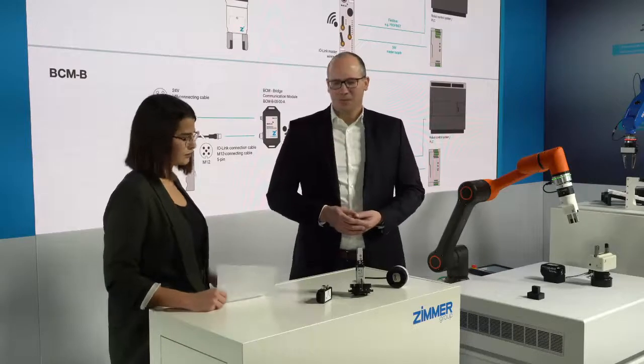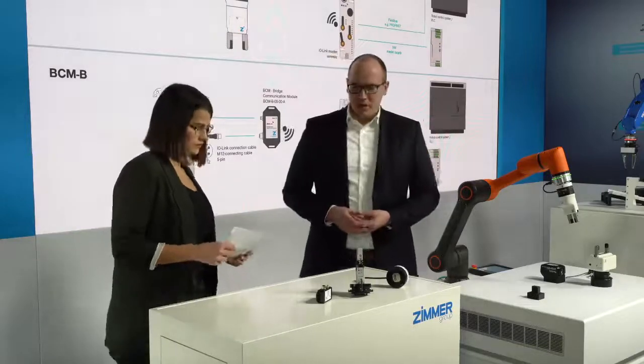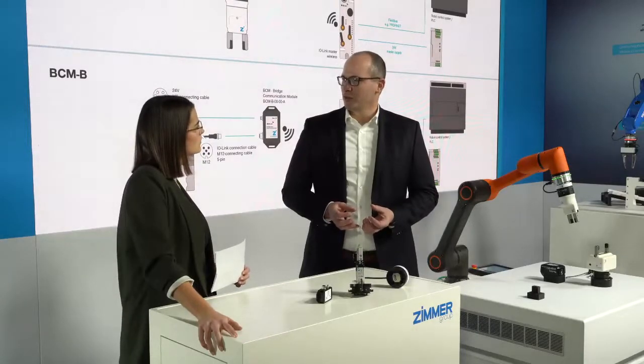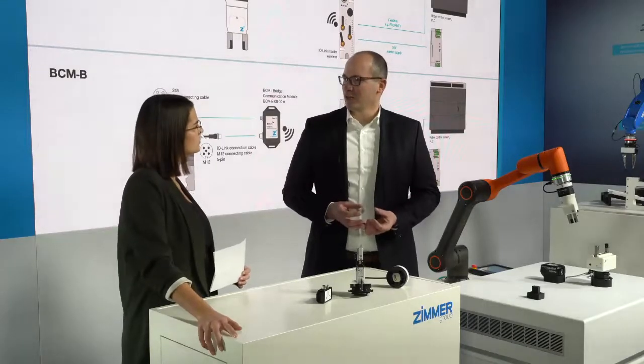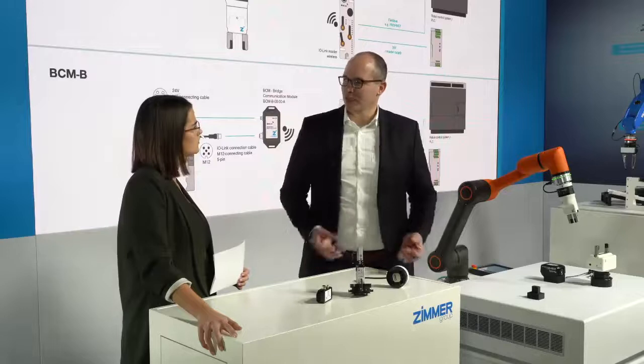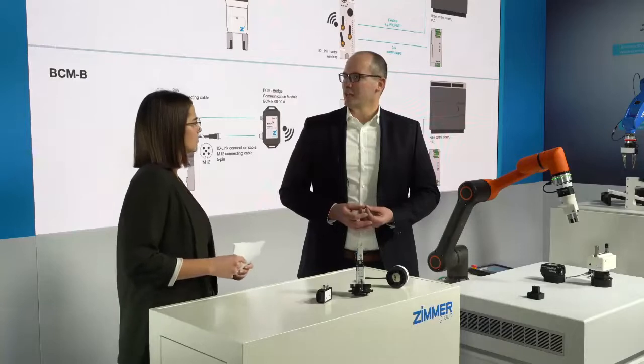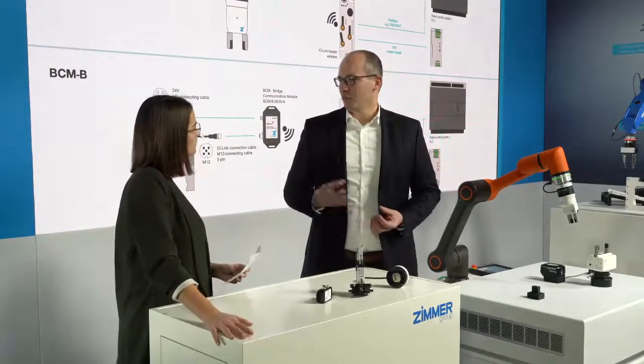Finally, it's a protocol that is more than 6 times more reliable than a Wi-Fi protocol or Zigbee protocol, for example. And it's a deterministic protocol. So it's wireless IO-Link, and it uses deterministic behavior that makes it really safe, because the data that is sent is acknowledged and processed directly when it has been sent. If something was sent incomplete, or if something got lost, the system will send it again, and the system will take care that everything arrives complete as needed from one point to the other.